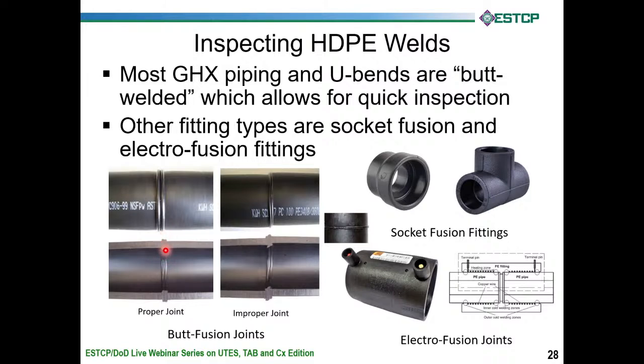And most of the time, if you put this in a test stand and pull on it, it will actually fail somewhere other than the joint, because the joint is sometimes as much as twice as thick. So if you get a nice, pretty joint like that, you know visually that it's very unlikely you're going to have a leak. If you see crap like this where the two pipes are misaligned, as you can see there, then you've got a joint that oftentimes is not going to hold. And I'm sorry, that picture's a little bit small, but there's another screwed up joint there.